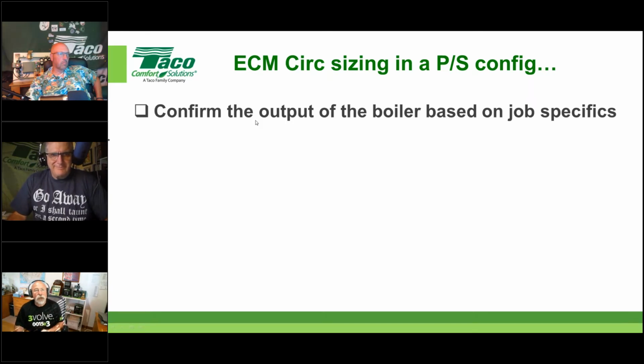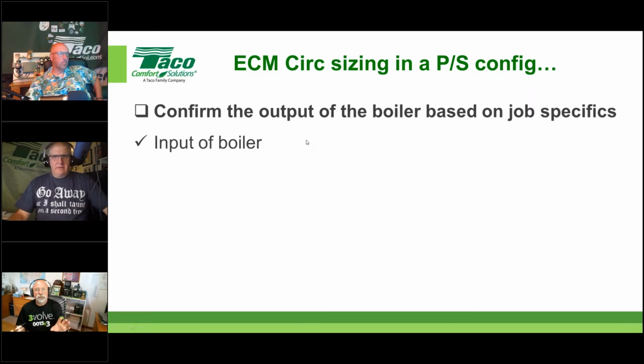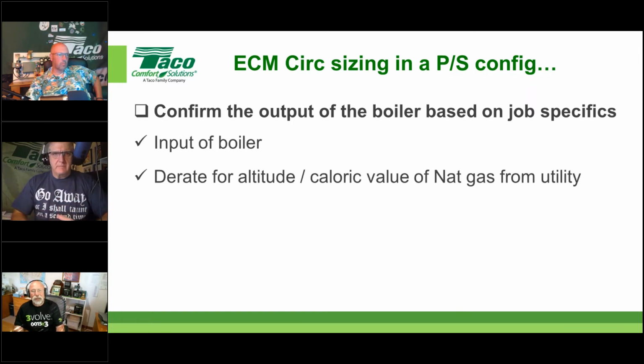I'm just showing you how you would come up with that information if you didn't have it from the manufacturer. We'll always need what the input of the boiler is. We'll need to derate that input based on altitude or caloric value of the gas that you're getting from that utility. Okay, so that's actually the first kick to the shins of what that boiler's capacity is doing.